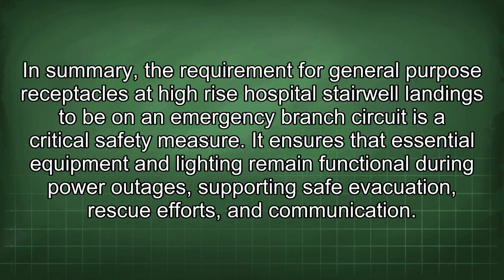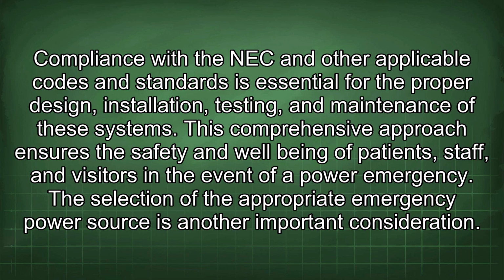In summary, the requirement for general-purpose receptacles at high-rise hospital stairwell landings to be on an emergency branch circuit is a critical safety measure. It ensures that essential equipment and lighting remain functional during power outages, supporting safe evacuation, rescue efforts, and communication. Compliance with the NEC and other applicable codes and standards is essential for the proper design, installation, testing, and maintenance of these systems. This comprehensive approach ensures the safety and well-being of patients, staff, and visitors in the event of a power emergency.